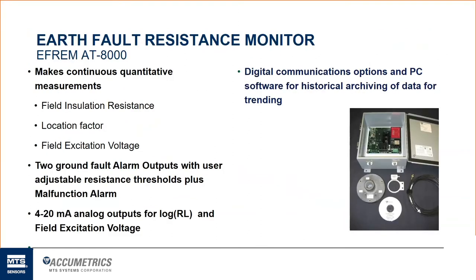So let's talk a little bit about the EFREM system. So the EFREM is our AT8000 series piece of equipment. That is the Earth Fault Resistance Monitor is what EFREM stands for. So that provides continuous quantitative measurements of both the field insulation resistance and the excitation voltage. Then what we offer is the location factor, which can help determine where on those field windings a ground fault has occurred. And I'll explain how we do that in the next slide.